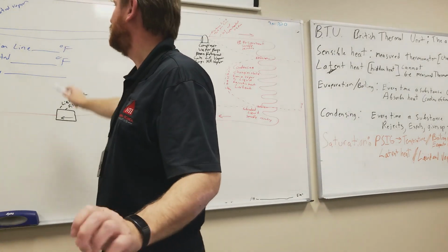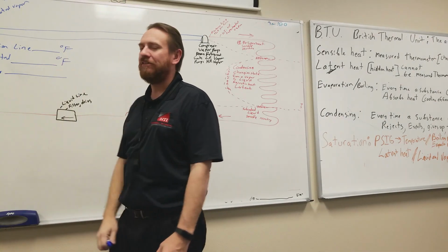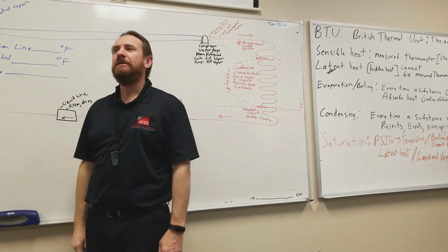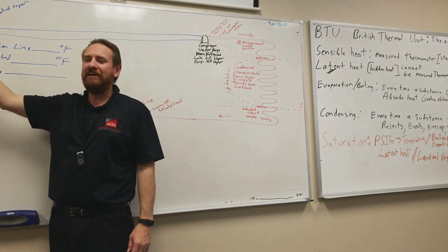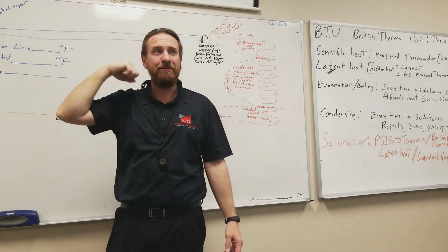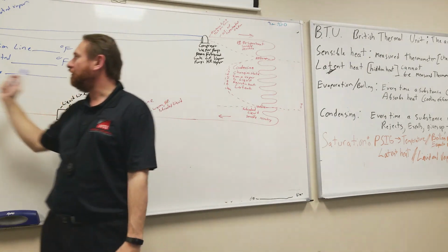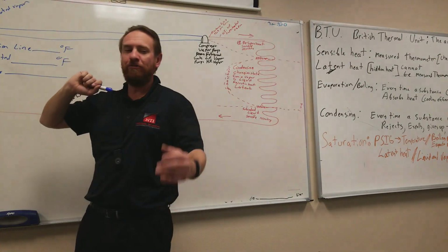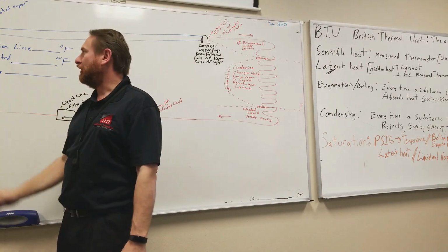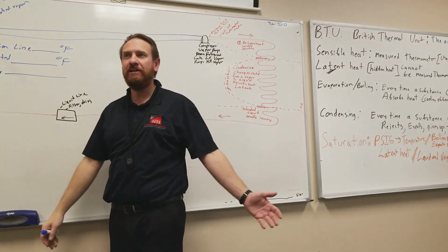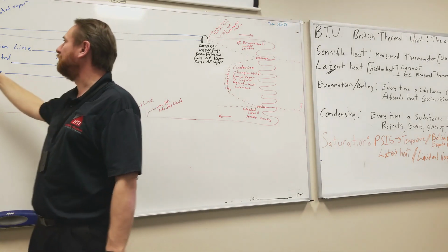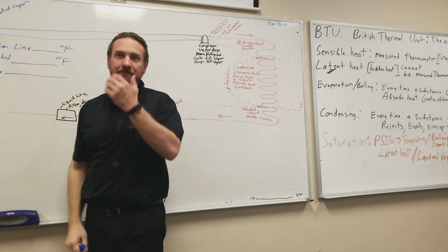If in any case you get a negative number here, there's something wrong. Maybe your clamp isn't clamping very accurately, or maybe it's a cheap clamp, or maybe the thermometer's off, or maybe you're using the wrong pressure conversion, or maybe the gauges are off. The lowest you can get down to is saturation, but that should be pretty well impossible, because what would negative superheat be?